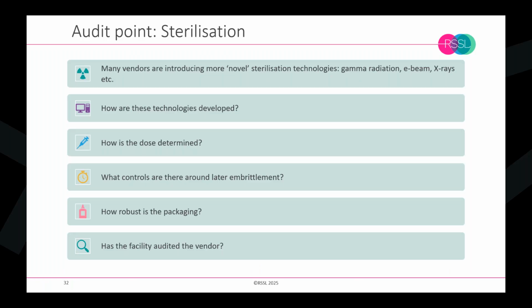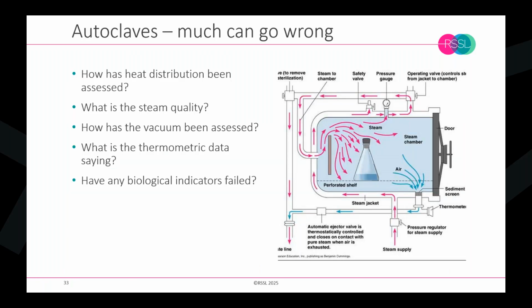And when we've used chemical and biological indicators, what's our understanding of those? How do we know that they've been used correctly? Did they have the right population, the right D value? And if you pick on a sterilizer like an autoclave, some useful questions to ask are: how has the heat distribution been assessed? What is the steam quality, particularly the steam dryness fraction? How do we know that the air is removed? And again, around the qualification method.